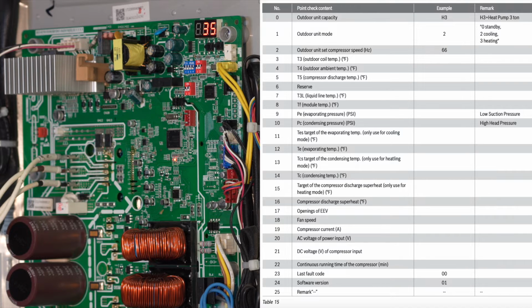Number 8 is TF module temperature. When we say module temperature, we're talking about the inverter board or the heat sink board, sometimes referred to as a radiator, but that heat sink big chunk of aluminum that dissipates the heat off the inverter board was showing 96 degrees at that point. Number 9 is the evaporator pressure or PSI. So that's actually your low side. If you were to have your gauges hooked up to it, that would be your low side. It was 116 at that point. And the next one, number 10, is our high side. It was 261. 11, if you remember back when we were talking about dip switches and target temperatures and so on and so forth, that 11 is your cooling target temperature, and it was at 46.